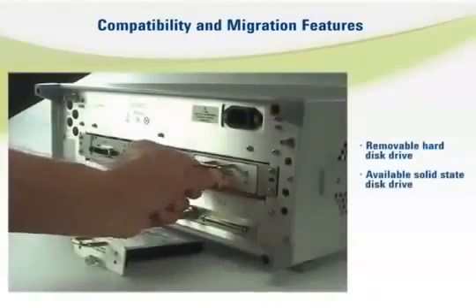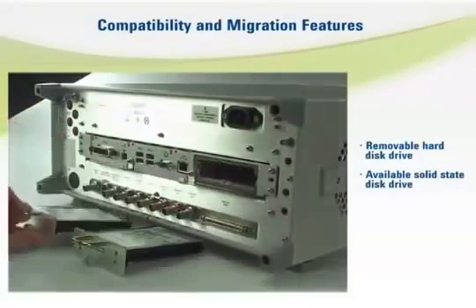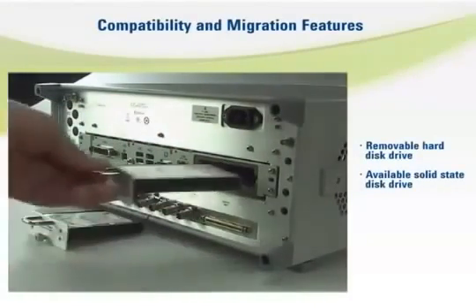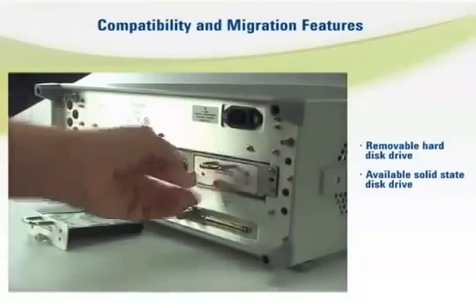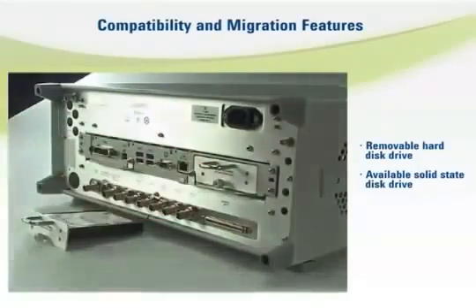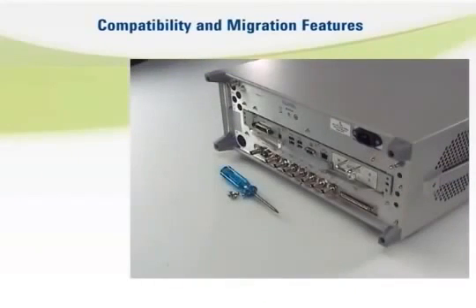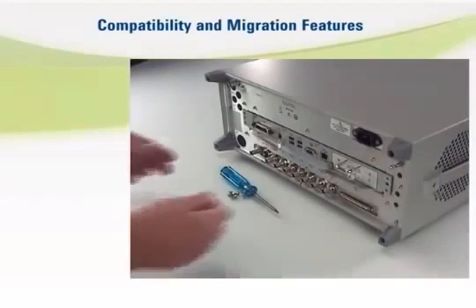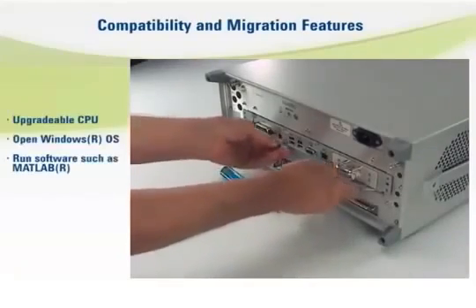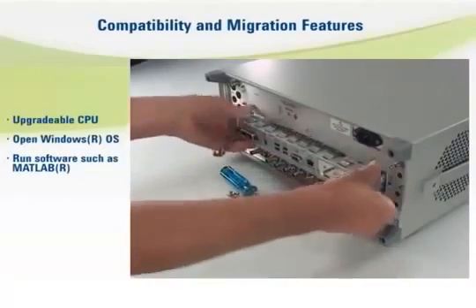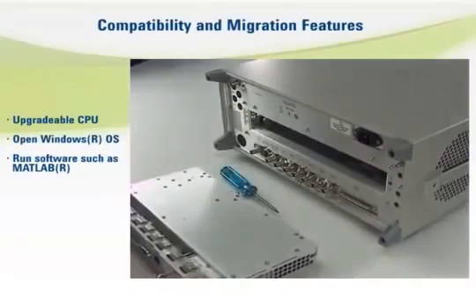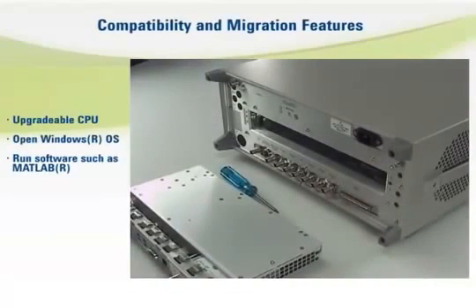Where data security is needed, the analyzer's hard disk is easily removed and another disk can be substituted for non-secure operation or calibration. This simplifies instrument sanitizing in sensitive applications. The hard disk can also be replaced with a solid-state disk. The analyzer CPU is easily removed for future upgrades and uses Open Windows XP Professional, allowing you to control other test system elements and operate software such as MATLAB.